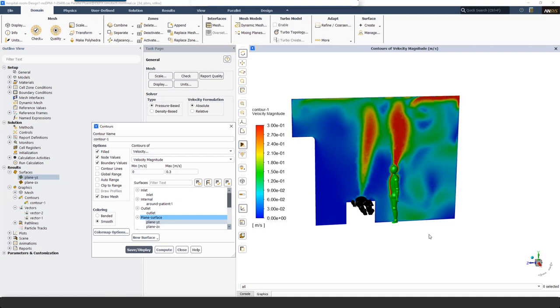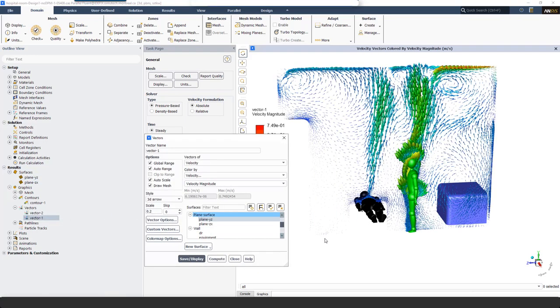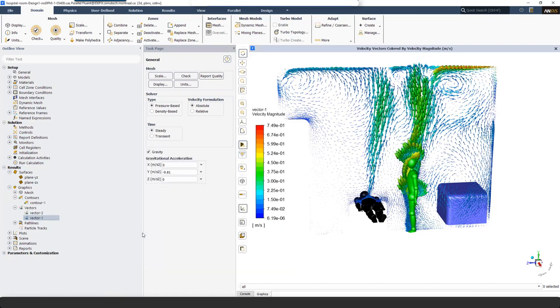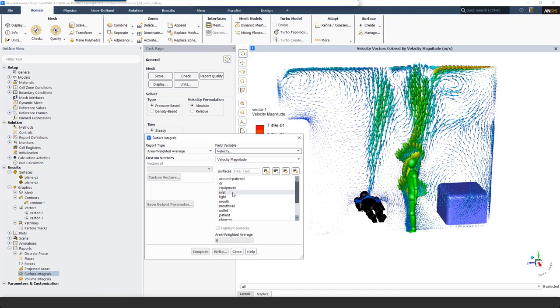To investigate results, I create a velocity contour at a plane through the middle of the room, adjusting the maximum velocity to 0.3 meters per second to identify low-velocity regions. As also seen in Discovery Live, there is still a low-velocity, low-circulation region to the left of the patient, confirmed by a vector plot. I also evaluate thermal comfort from surface integrals: the velocity around the patient is around 0.04 meters per second and the temperature is 20.2 degrees Celsius.